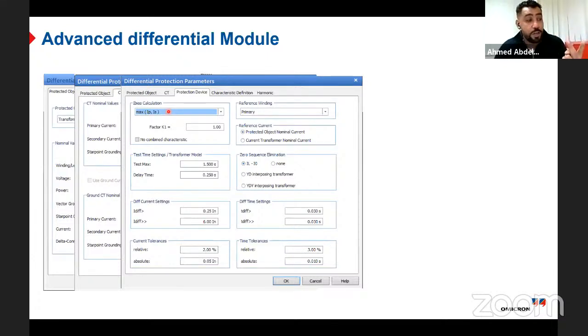In Siprotec 4, the equation was I primary plus I secondary over K. And here K might be 1, might be 2. It is based on the relay. But in Siprotec 5, it is different: maximum of IP and I secondary. So you need to define the K factor from the relay manual. No combined characteristic. This is a special application for ABB relays, RET 670. You will see in the next slide how it looks like.